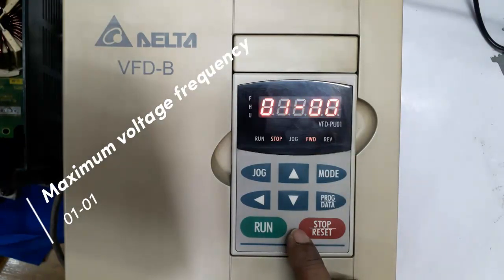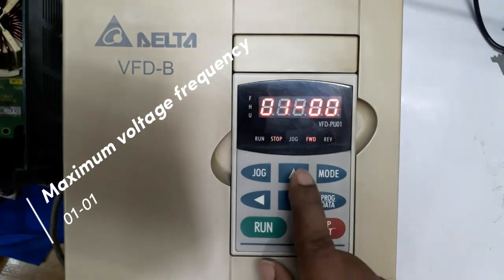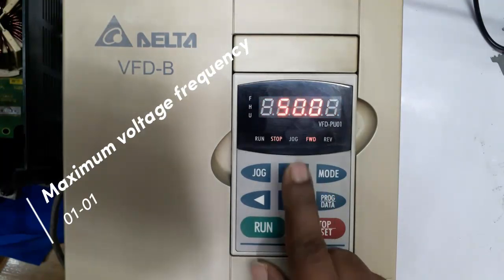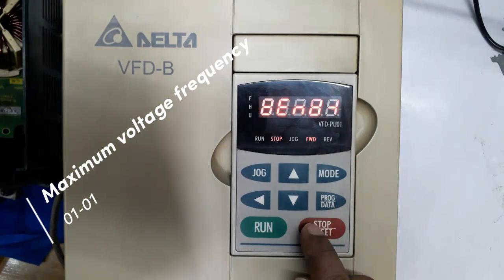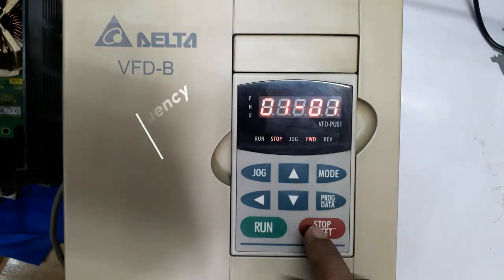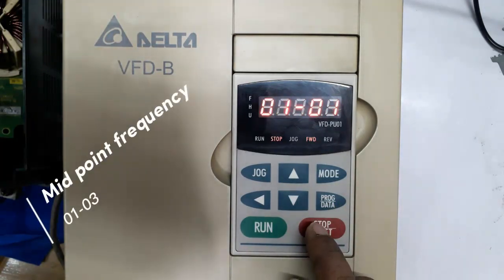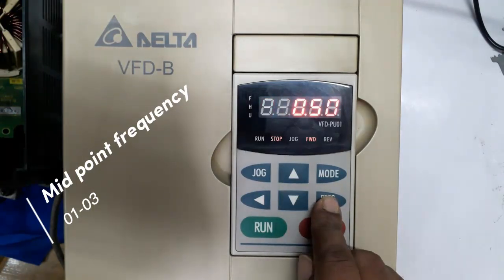Default setting is 60 Hz. Parameter 1-01, maximum voltage frequency. You can set here as your desired level. Parameter 1-03, midpoint frequency. Our default setting is 0.50.